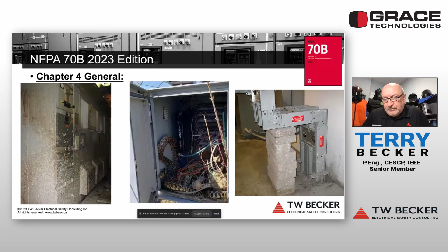The National Electrical Code, on the far right, I don't think would sponsor using concrete blocks to support your high voltage busway. We've got water coming in, and plastic being used to protect the equipment from water ingress. I call this the magic box—and that was actually energized. I'm amazed this facility had reliability and didn't have a lot of faults occurring.